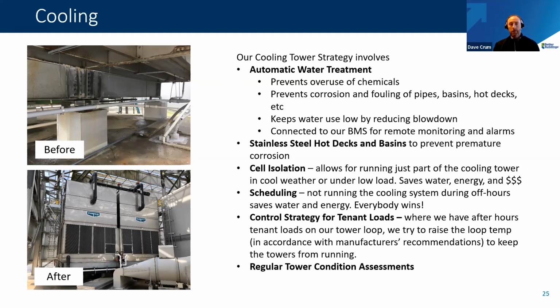We've also been able to utilize those water treatment controllers for some BACnet points. We monitor flow going into our cooling towers, and also monitor the cycles of concentration and similar data in our building management systems. That's been a real big win for us.